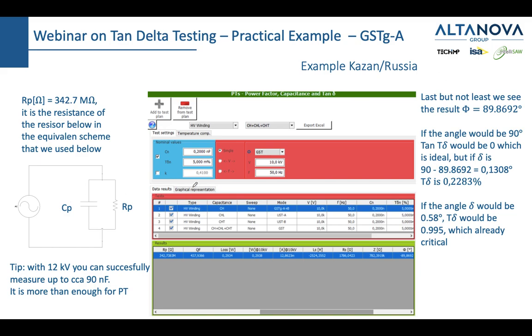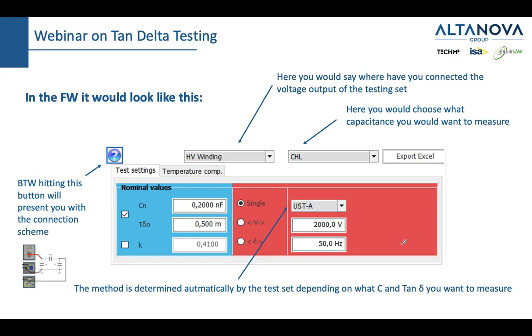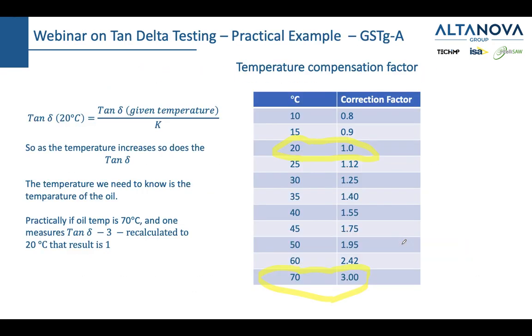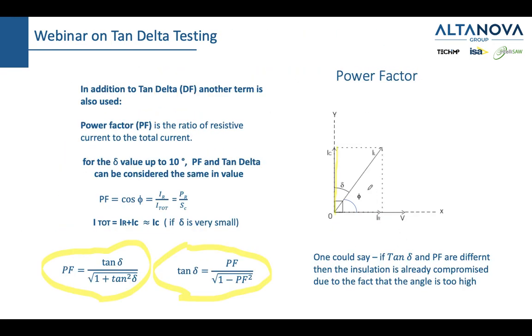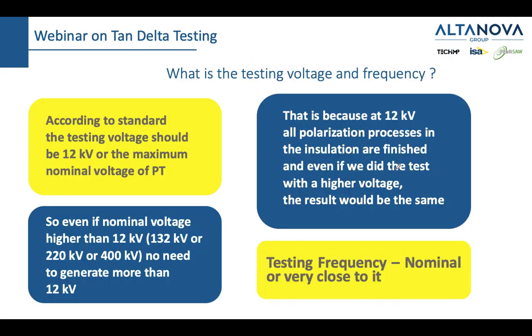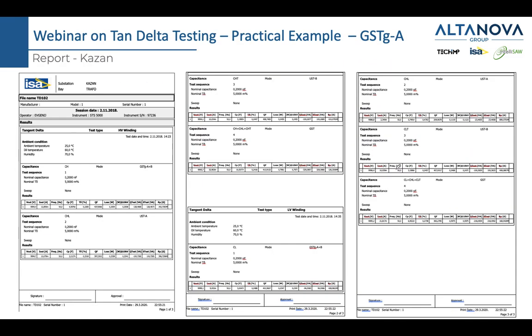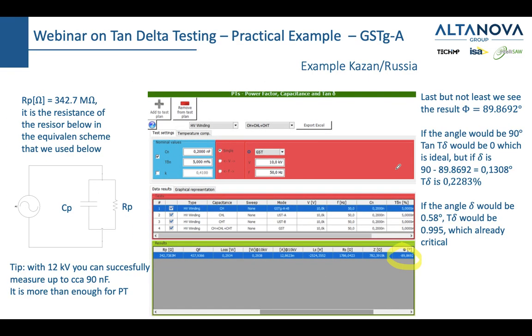Also, one thing which I like to mention is that here you have the angle phi. So just to remind you, the angle phi is not the angle delta. Angle phi is this angle here. This angle should normally be 90. In this case, it is not 90, but it's 89.8692. So it's only 0.13 degrees less than ideal.